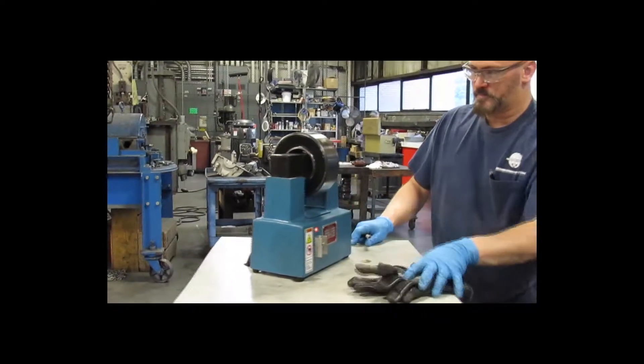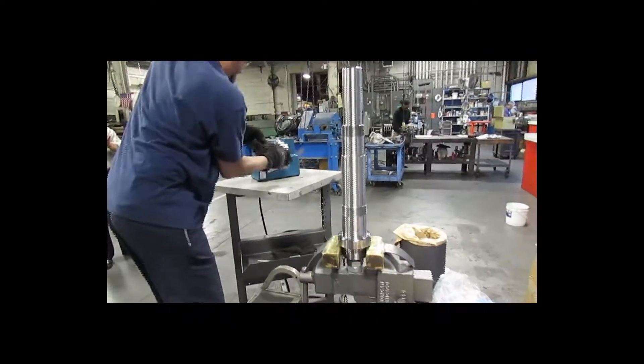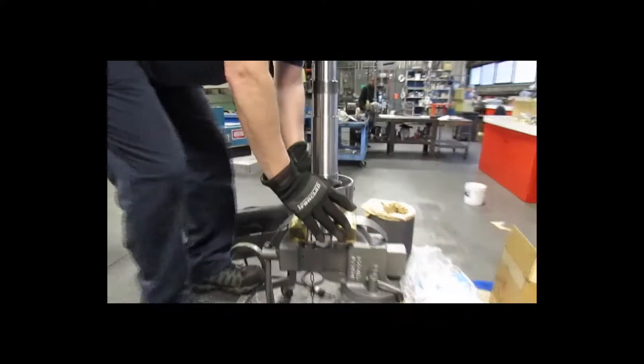The induction heater is energized. When the bearing reaches the proper temperature and the bearing crayon melts, the bearing must be installed immediately onto the shaft to prevent it from binding on the way down. The bearing is fully seated.